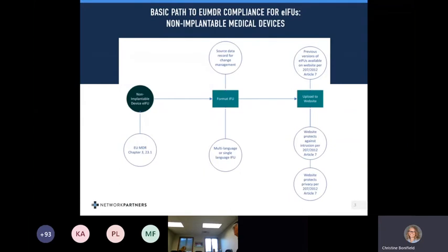To meet the most basic requirement, you just need to post a PDF on a website. Post this PDF as is, or you can reformat it. You can post a copy of your folded up gas station roadmap style IFU to a website and meet the letter of the law. But your notified body may take a dim view of your approach. Since we don't have a lot of history with the notified bodies' decisions from MDR audits yet, that's a risk you'll assume if you take this approach. Evaluate that risk, and you may decide that some reformatting of the IFU is appropriate.